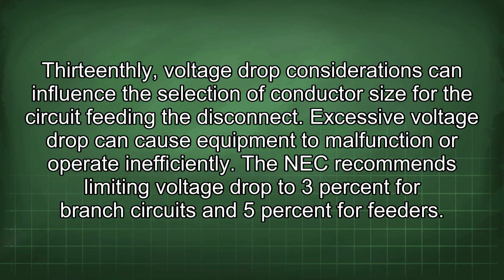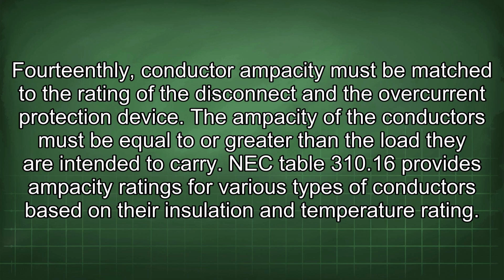13thly, voltage drop considerations can influence the selection of conductor size for the circuit feeding the disconnect. Excessive voltage drop can cause equipment to malfunction or operate inefficiently. The NEC recommends limiting voltage drop to 3% for branch circuits and 5% for feeders. 14thly, conductor ampacity must be matched to the rating of the disconnect and the overcurrent protection device.